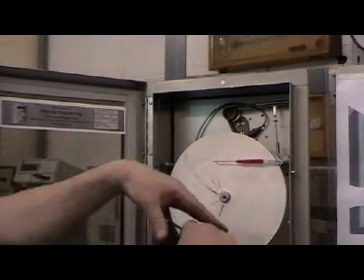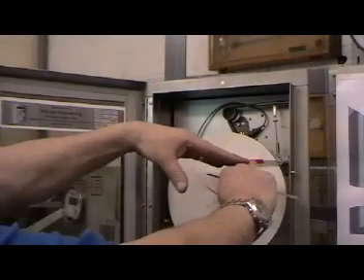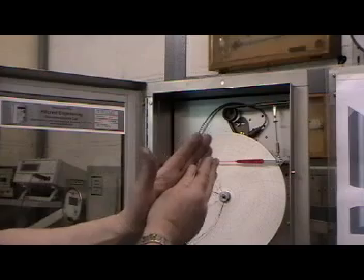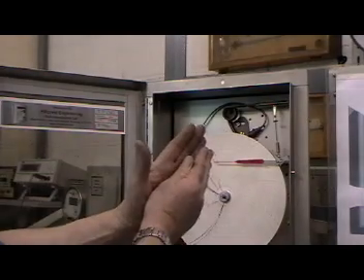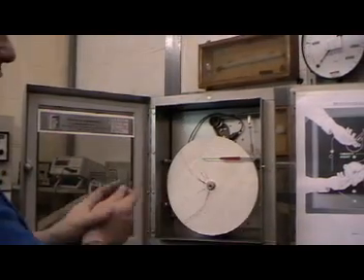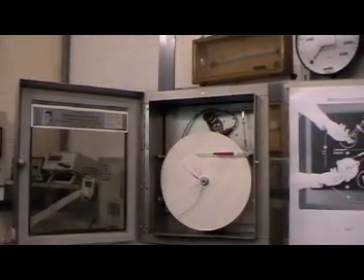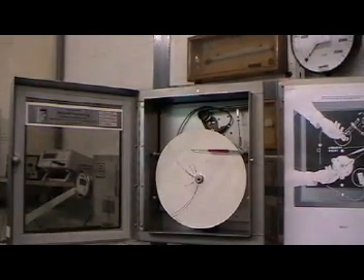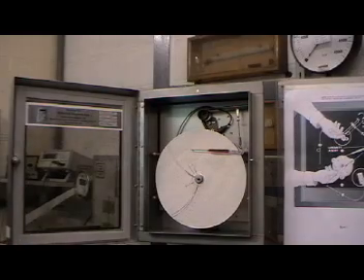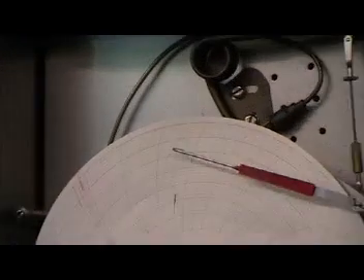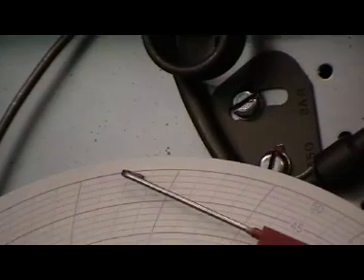And vice versa, if the pen was the opposite way around, we'd have more movement in the second half of the chart than the first half of the chart. So, quickly going up, 2500 was 2600. And then going to 5000, we're a little bit short on span.